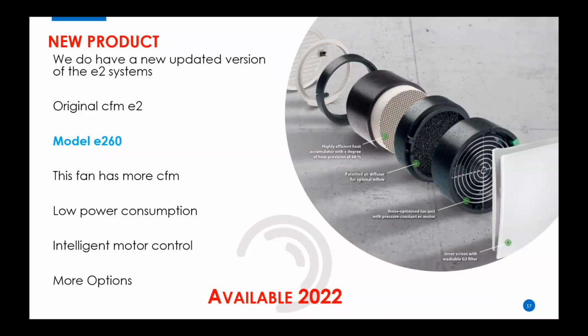Heat recovery ventilator takes the sensible heat - picture people in a space, that's the best way to describe it. That moisture in the space from people, you need to remove. If you have a shower in your bathroom and get condensation, you need to remove that. An HRV unit cannot do that, but an ERV unit can. It's a coating on your ceramic wheel - in larger units, it's a coating on the actual heat exchanger that allows it to do that. It takes the droplets and moisture out of the air and transfers it out, where an HRV will not transfer the moisture out of your building.